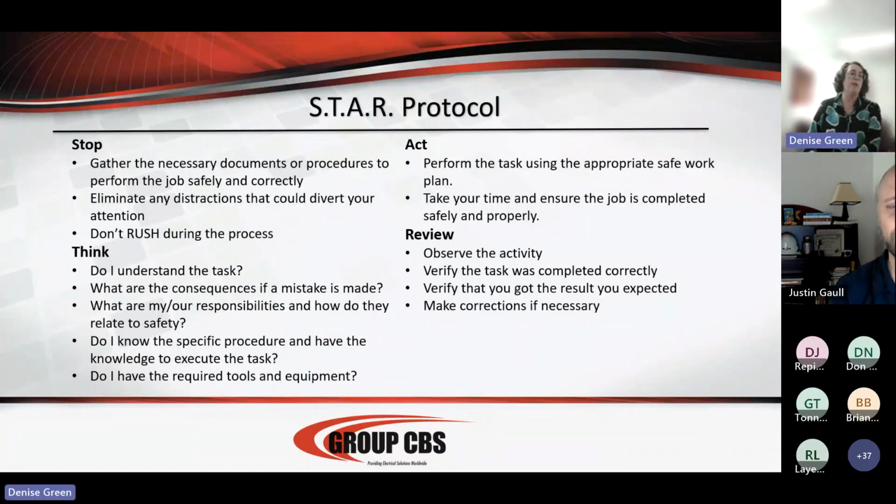Right. So in 2015, the NFPA 70E had a note about any work done over 40 calories should require extra planning, decision-making, and care. When that note came out in the 2015 NFPA, it had kind of an opposite effect. It made people think that, well, nothing below 40 is really that big of a deal. So they removed that from the standard.